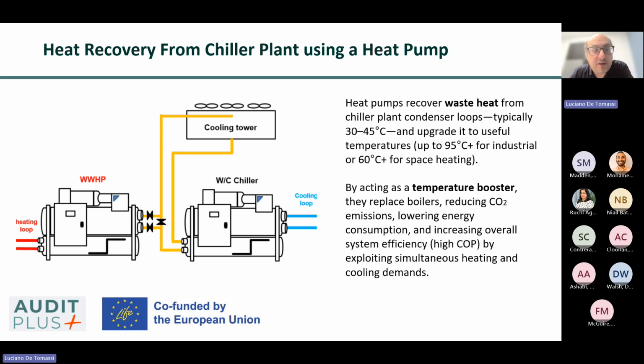Heat recovery from chiller plant using a heat pump. Heat recovery from a chiller plant or refrigeration system using a heat pump is based on capturing low-grade waste heat from the condenser loop and upgrading it to a higher, more useful temperature level. In a typical chiller plant, heat is rejected at the condenser into a cooling water loop or dry cooler circuit at temperatures commonly in the range of about 30 to 45 degrees Celsius. This heat is usually discharged to ambient conditions, even though it still contains significant usable energy.